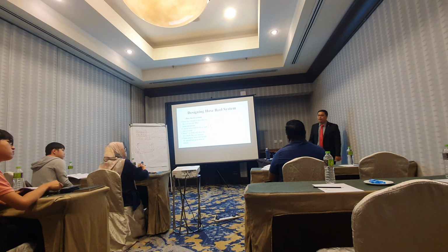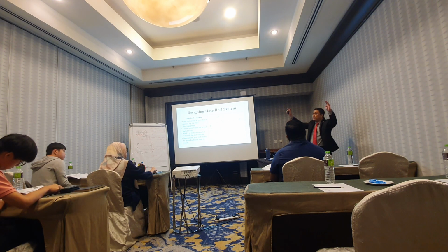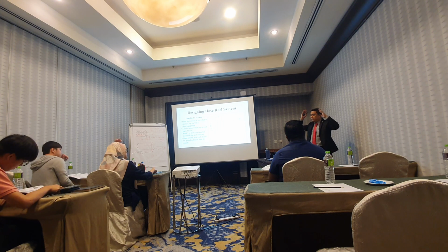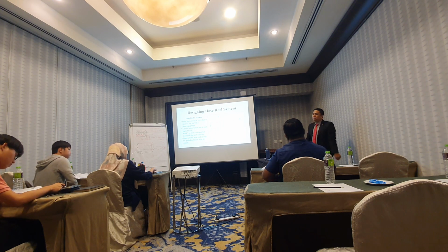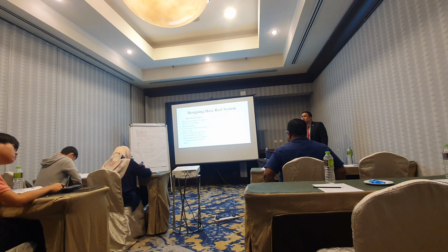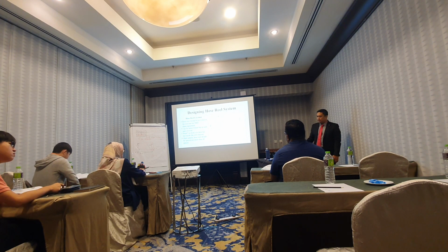Kalau sebelum ni, normally kita design up till the habitable area lah. Maksudnya area yang digunakan oleh orang. If we have an M&E at the top of our building, normally they are non-habitable area. So kita tak letak hose reel kan. But for the new requirement, we need to have the hose reel lah. Yang ni you boleh check yang paling baru lah. If it's a new submission, you kena ensure that they are following this law.